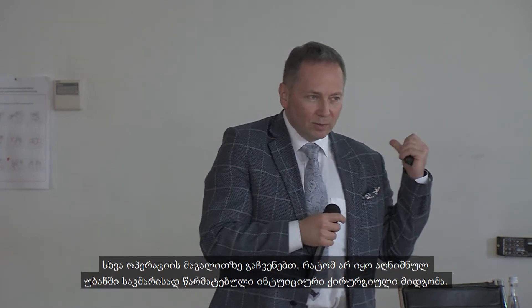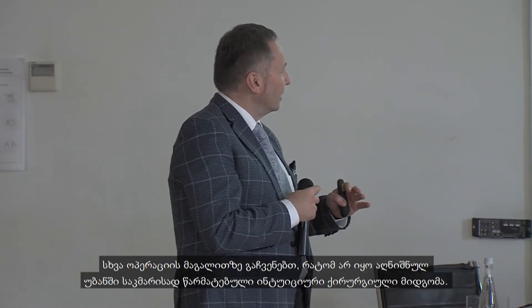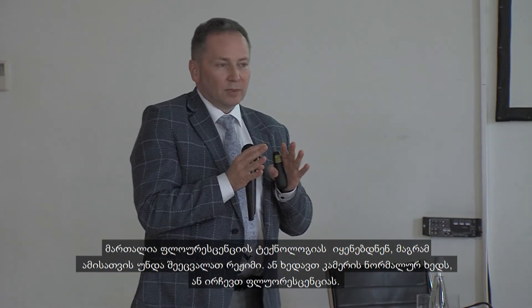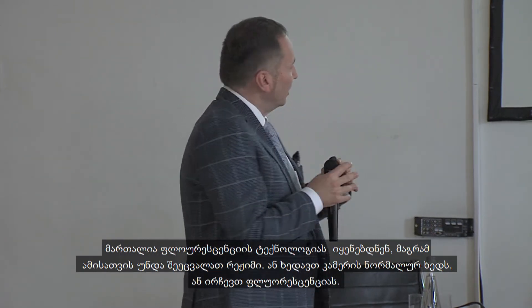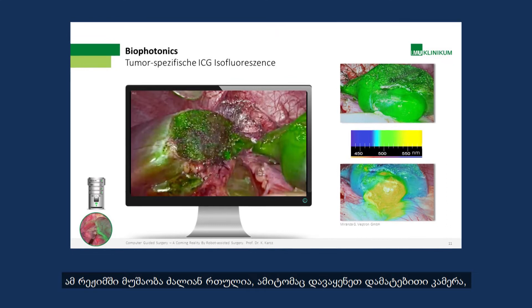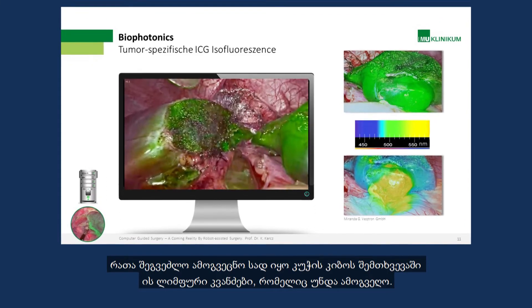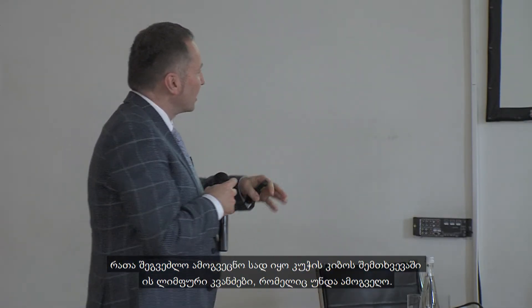This is another operation. Intuitive Surgical was not so successful in this region — they have the fluorescence technology, but you had to switch the view. You could see either the normal camera view or only the fluorescence, so in that mode you cannot operate. That is why we added an additional camera to work around the situation, and we could then recognize where the lymph nodes were for stomach cancer removal.